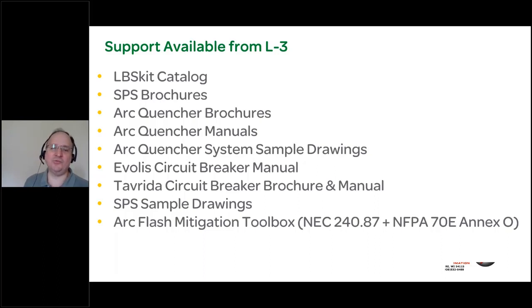If you're interested in that exciting Tavrida circuit breaker, we have both brochures and manuals on it. We have sample drawings in AutoCAD format that we can sanitize from similar projects and send you. So if you're a consulting engineer or you're just trying to work up an initial design, you don't have to start from ground zero. We're here to support you in your engineering design efforts, not only to reduce the cost of the switchgear itself, but to reduce the amount of time it takes to design and implement this type of solution.